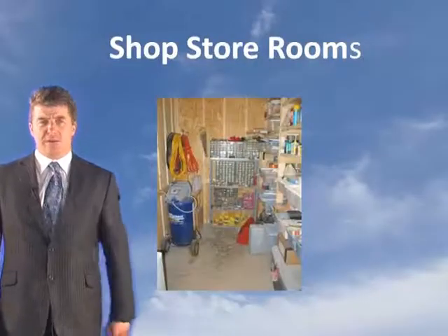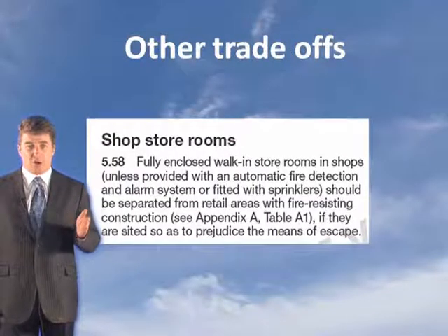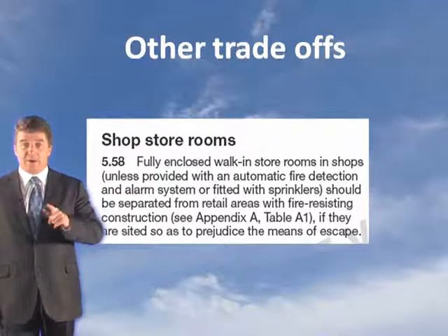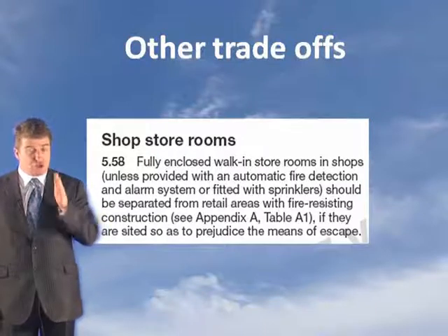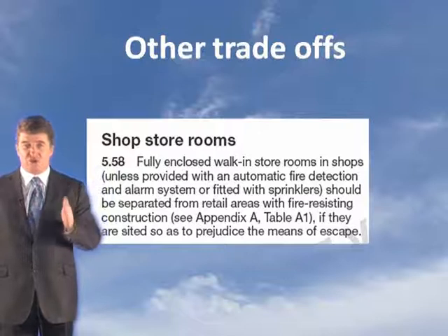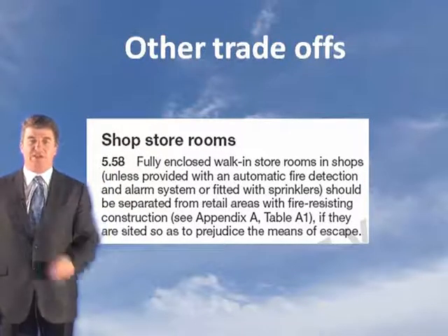Shop storerooms, then. What can they allow? Fully enclosed walk-in storerooms in shops, unless they are provided with an automatic fire detection and alarm system or sprinklers, should be separated from the retail areas with fire-resisting construction if they are sited so as possibly to prejudice the means of escape. So if you put sprinklers in, you don't have to do this with the shop storerooms.